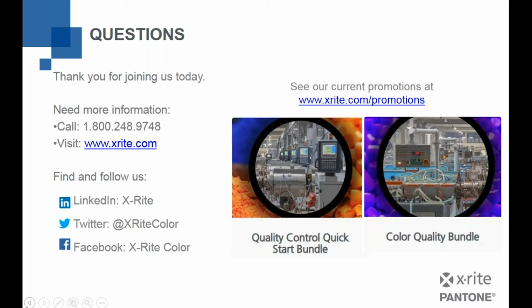So when I put the sample up there, that light shining from that spectrophotometer onto the sample is going to penetrate and see the color of, let's say I have ink on paper. It's going to see the color of the ink, but it's also going to pass through that because it's transparent and see the color of the substrate. So if I take the exact same ink, print it on 3 different substrates, and measure them, I'm going to have 3 different colors. And visually, you may too. It's just that a spectrophotometer is probably much more sensitive to that than the human eye is.